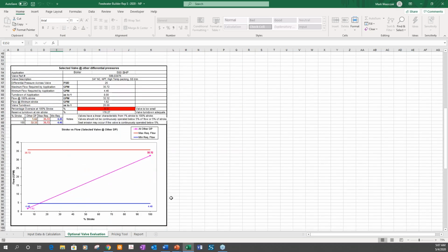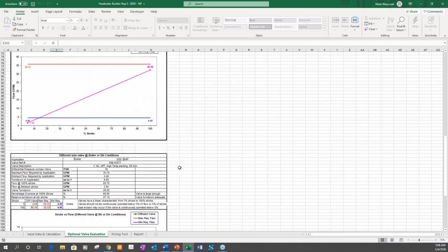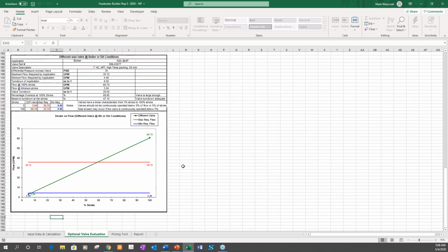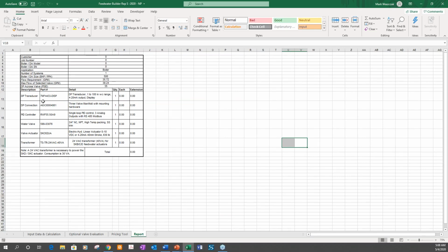The second chart is based on the 25-pound differential for a 3/4 inch. In this case, the 3/4 inch valve will be too small to meet the demand. And finally, the third chart allows us to see we selected a 1 inch valve versus a 3/4 inch based on the initial conditions, and it tells us, yes, this valve will be okay as well. So it gives you multiple options in terms of how you want to go about sizing it. Finally, if you click on the report tab at the bottom here, it'll give you an entire list of all the components that you need for your level control system.